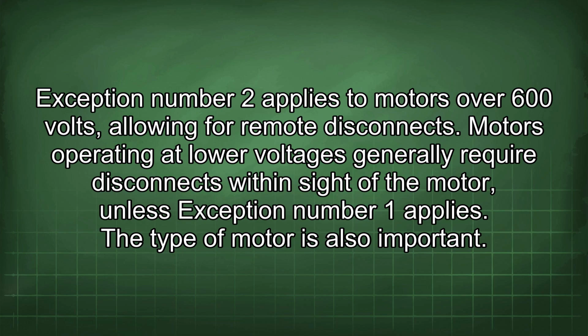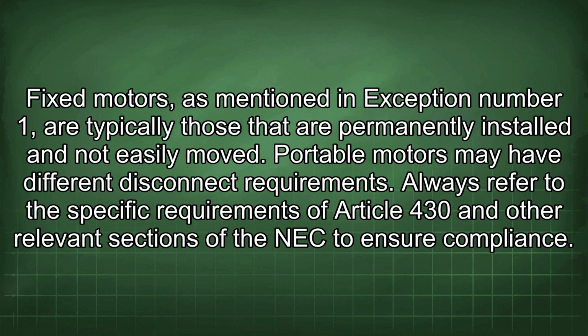The type of motor is also important. Fixed motors, as mentioned in exception number 1, are typically those that are permanently installed and not easily moved. Portable motors may have different disconnect requirements. Always refer to the specific requirements of Article 430 and other relevant sections of the NEC to ensure compliance.